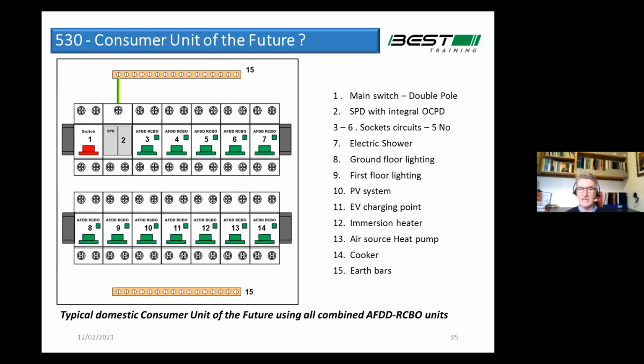They're too small. And I've been involved and I've done reports on at least one case in my career where an apartment went on fire. The consumer unit went on fire in the apartment and ended up like a ball of carbon lining the floor of the apartment. Thankfully nobody was injured as a result. It was down to a loose connection in the consumer unit. Had that been a metal consumer unit secured to the wall, I don't think it would have collapsed off the wall and probably would have contained the fire a little bit better. So that's one of the things that's dealt with.